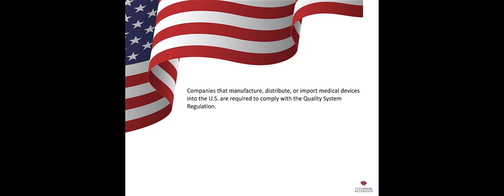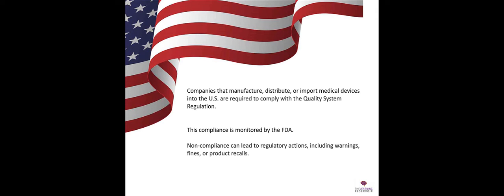It is very important that companies understand that if you are manufacturing, distributing, or importing medical devices into the US, you have to comply with the Quality System Regulation. The FDA will monitor you and your compliance, and if you're found to be non-compliant, that will lead to regulatory actions including warning letters, fines, or even product recalls. So you have to understand the requirements of the QSR.